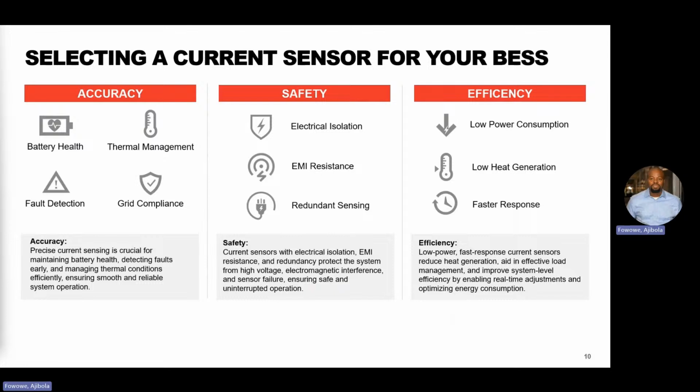The voltage drop reduces the overall system voltage and can create inaccuracies in the current measurement, particularly in applications where precise current control or voltage control is critical. That's, for example, in grid connection or inverter control. Since the Hall effect sensors do not directly introduce a voltage drop into the circuit, they offer a more accurate and efficient method of current measurement without affecting the system's operating voltage.